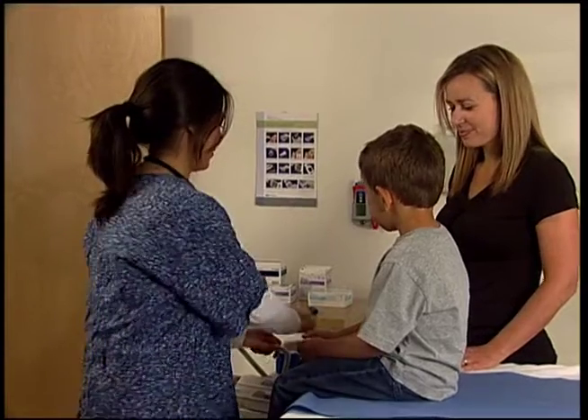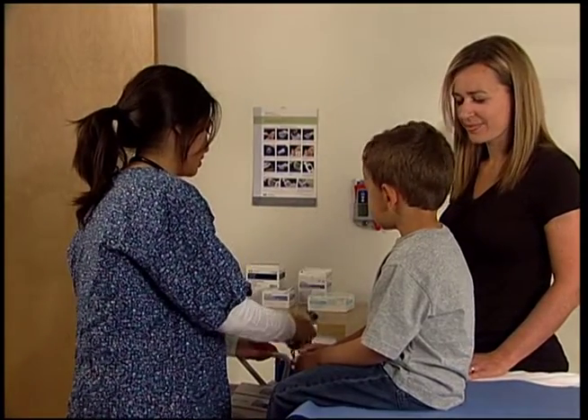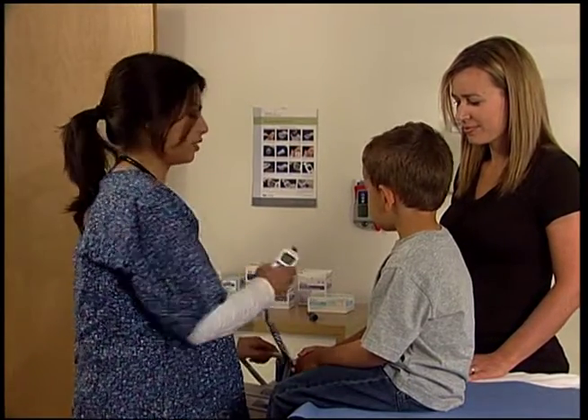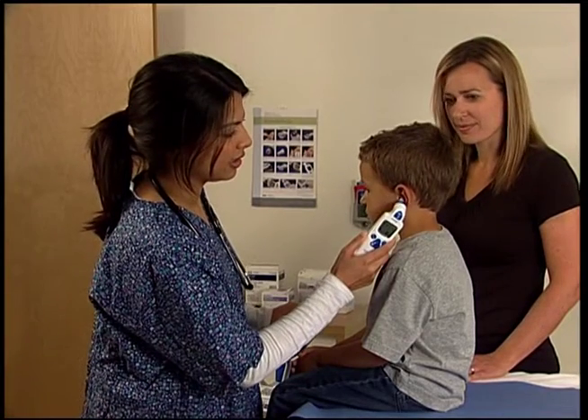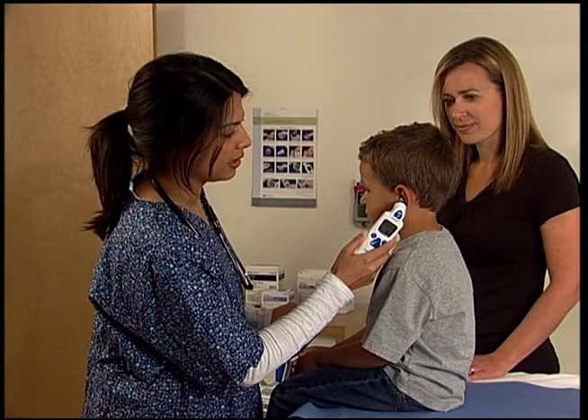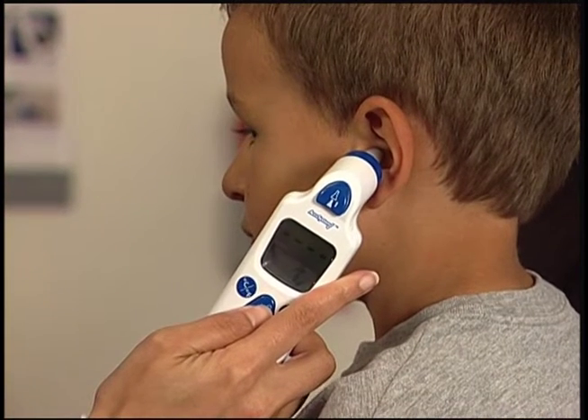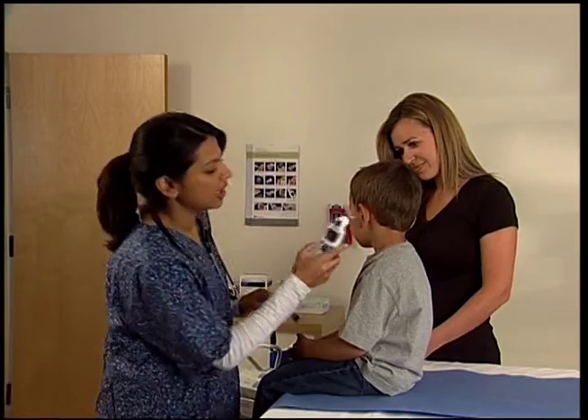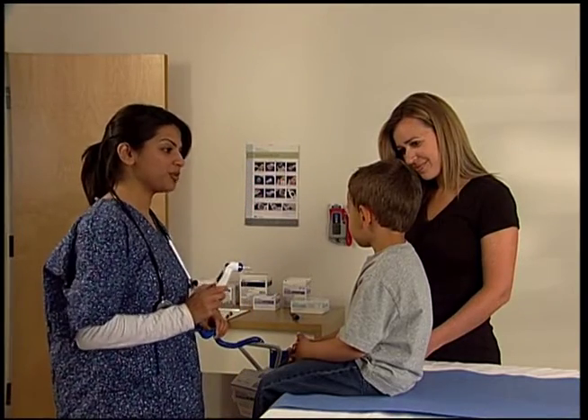Apply only gentle pressure for children and especially infants to avoid compressing the very soft tissue in the ear, blocking infrared energy from reaching the probe tip. Once seated in or over the ear canal, press the scan button to take your reading. Discard the probe cover once you have completed the reading.